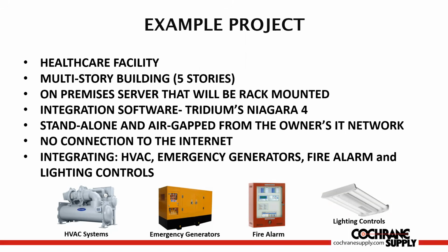And this was an actual project from a healthcare provider. It was a multi-story building, 5 stories, no connection to the internet. It was an on-prem server that's going to be rack mounted. And we were using Tridium's Niagara 4, of course. And like I said, it's standalone, its own server, and it's totally air-gapped from the owner's IT network. So there's no connection whatsoever. And we weren't concerned about cybersecurity to that extent because we weren't connecting to the internet.